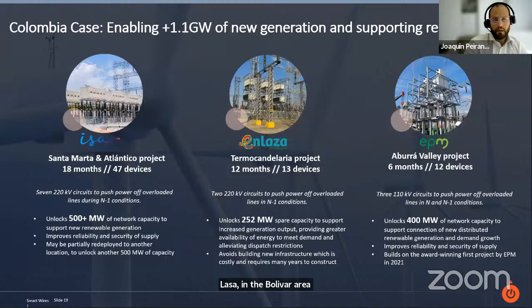The key facts I want to highlight here are the speed and the effect of this type of project on the network. All of these were used to mitigate thermal overloads, either impeding new generation from connecting to the grid, or to just improve grid reliability overall. Starting from the left with the ISA examples, we delivered about 47 of these modules, installed in 7 different circuits, all at 220 kV. Those projects took each about 18 months, from order to in-service, and they're creating about 500 megawatts of capacity for wind and solar to connect.